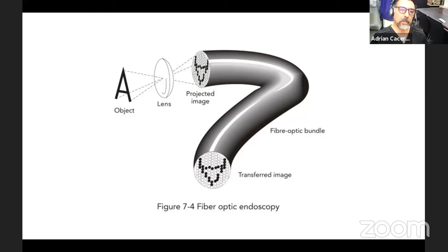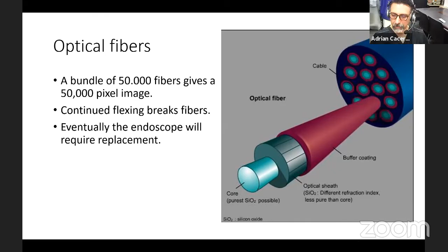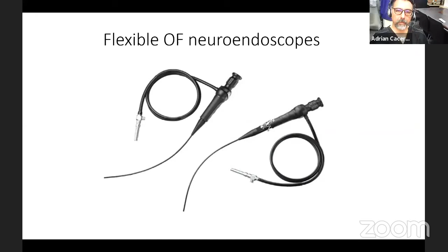This is the principle of how you put together the image on a fiber optic endoscopy. So it's a number of rods that conform the image. The problem that you have with optical fibers is that as the endoscope bends back and forth, with time you'll start to see these black dots in your image, which means that the fibers have broken and are no longer transmitting the image. So they decay with time, and eventually you need to replace them. Of course, the other choice that I show you, which is the camera in front of the flexible endoscope, is very nice, but also very expensive. So these are two kinds of flexible endoscopes.